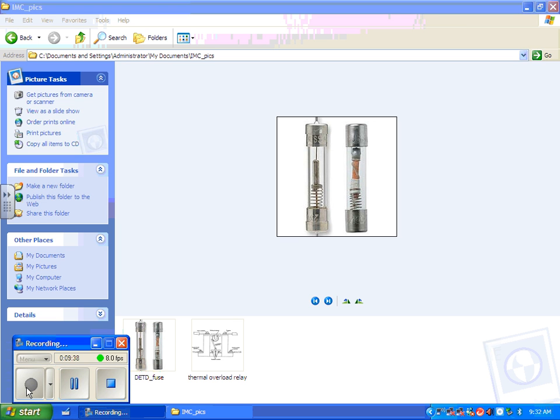The overload contacts in that overload heater we looked at on page 37? The overload contacts, very often, they only have one overload contact. In the modern ones, there'll be 3 overload heaters and 1 overload contact. In some of the older ones, it's 3 overload heaters and 3 overload contacts. And that's okay, but if you see the 3, you know that they've got to be wired in series, so if one drops out, they all drop out. Drops out the control circuit. Okay, in protecting a large motor, often we'll use a current transformer to step down the current so it's not quite as dangerous, to sense it and evaluate the overload of it.